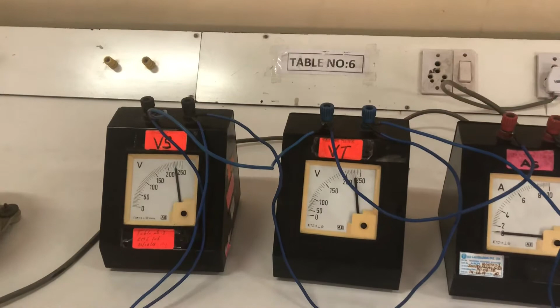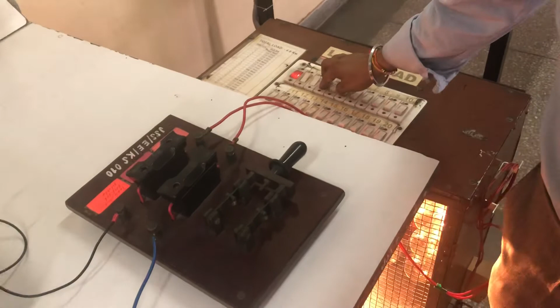Now we need to calibrate the ammeter. To calibrate the ammeter, we should load the lamp. So first we are loading the lamp - this is our lamp load. Yes, switch on the lamp load. We are switching it on, and now I should observe the standard ammeter reading.